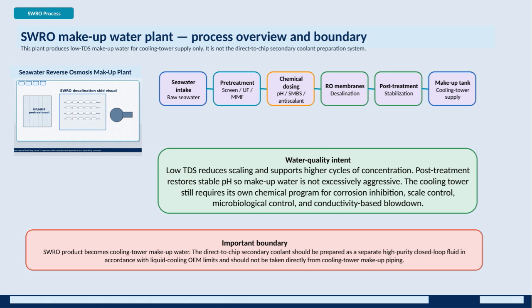Although the water is stabilized, the cooling tower itself requires its own chemical management program for corrosion control, scale inhibition, microbial control, and blowdown based on conductivity. A key point to remember is the boundary of the system. The SWRO plant supplies only the cooling tower makeup water. The direct-to-chip secondary coolant must be prepared separately as a high-purity, closed-loop fluid following the specifications of the liquid cooling equipment manufacturer. It should never be taken directly from the cooling tower makeup line. This separation is critical to ensure the performance and reliability of the entire cooling system.